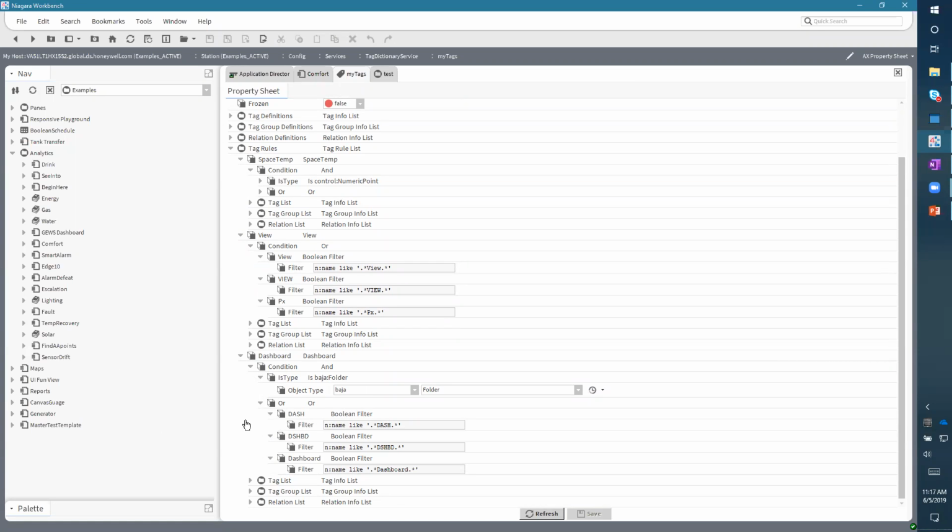And you'll see in the palette, you have all kinds of ways of saying, hey, it has to be a device. It has to be on the BACnet network. So anything that you build in your rule to eliminate and fail fast is a good thing, because then it won't chug through the entire database applying those names, okay? So with that, that's tagging.